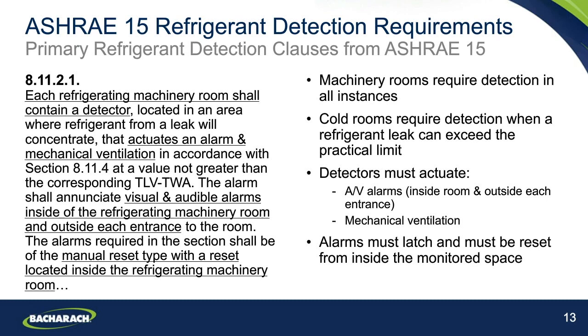And that leak should be at a value no greater than the corresponding time-weighted average levels, which typically tend to conform to the occupational exposure limits we touched on earlier. Key things here to note are that in the event of an alarm, visual and audible alarms shall be activated inside the machinery room and outside of each entrance. So it's important to note that the entrances to the space also need to provide a warning to personnel, not just within the space. And there was a note in there as well that the alarms should be reset manually from within the machinery room.